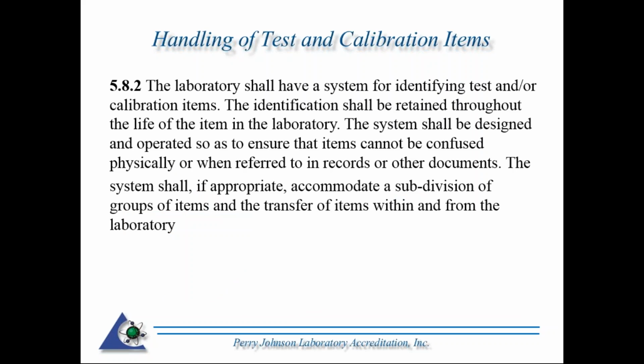Okay, that is 5.8.1. So moving on to the second clause, 5.8.2: the laboratory shall have a system for identifying test and or calibration items. The identification shall be retained throughout the life of the item in the laboratory. The system shall be designed and operated so as to ensure that items cannot be confused physically or when referred to in records or other documents. The laboratory shall, if appropriate, accommodate a subdivision of groups of items and the transfer of items within and from the laboratory. So this particular clause, as you can see, is primarily dealing with the identification of items that you are testing or calibrating.